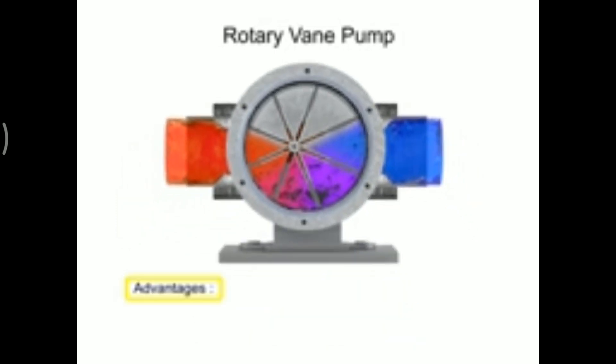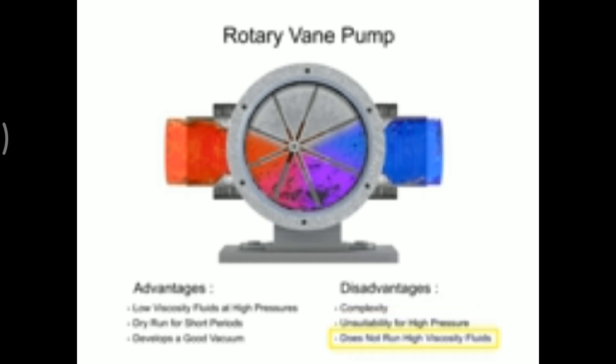The advantages of vane pumps are that they can handle low viscosity fluids at relatively higher pressures, can dry run for short periods, and develop a good vacuum. The disadvantages include complexity and their unsuitability for both high-pressure and high-viscosity fluids.